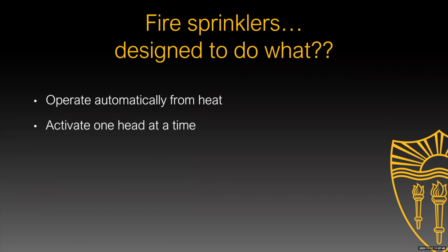Okay. The other thing is that you guys see Hollywood movies where they show that anytime there's a fire, all of a sudden all the sprinkler heads go off at one time. That is false in regards to a fire sprinkler system. Now, if you're talking about a deluge, which we'll talk about a little bit later, that's a different story. But normally the intent of fire sprinklers is to try to activate one, maybe two or three, kind of keep it localized where the fire is. So really the activation is focusing on where that fire is.